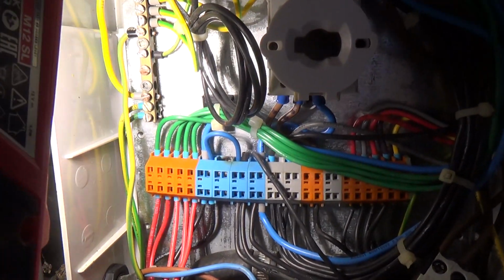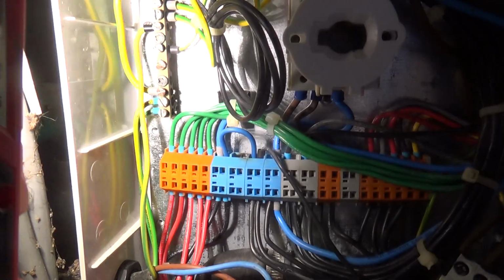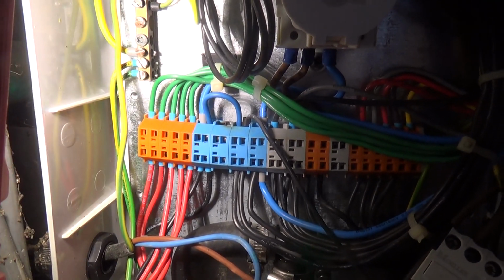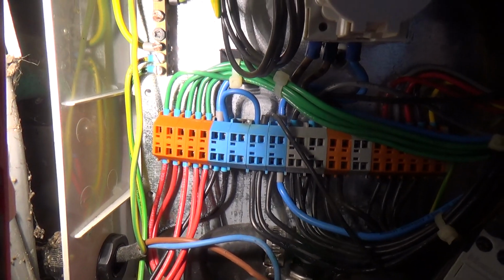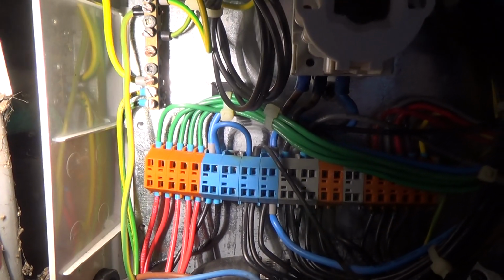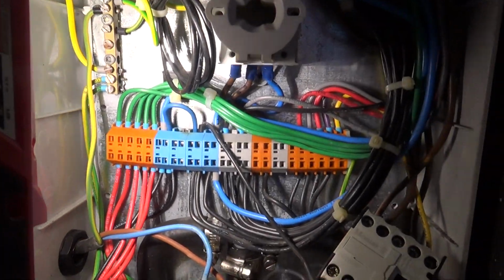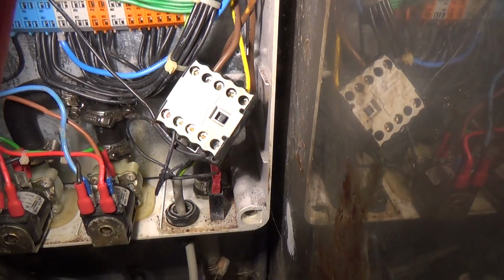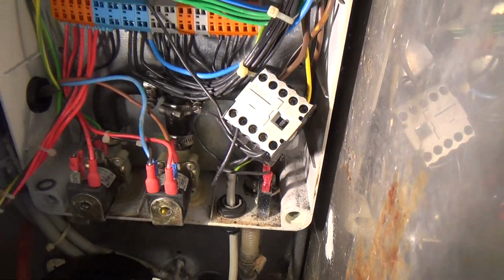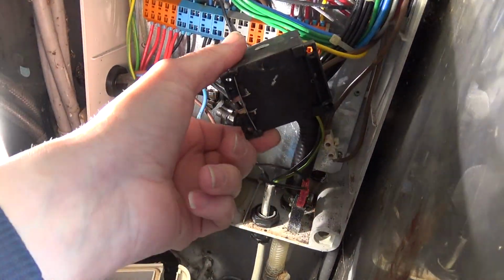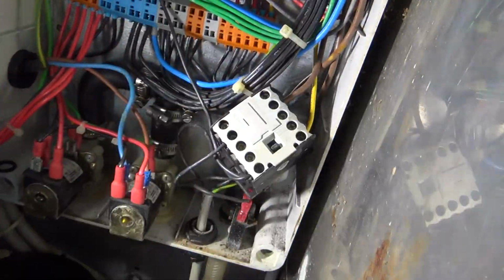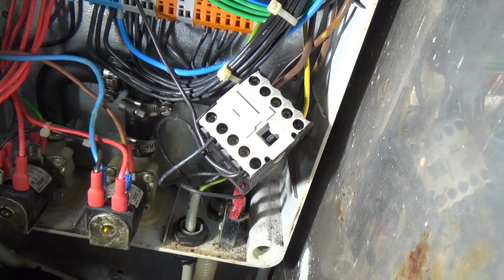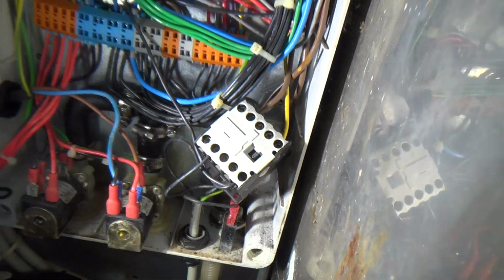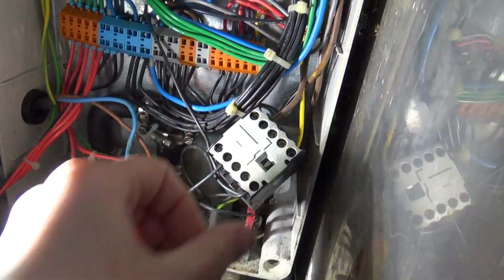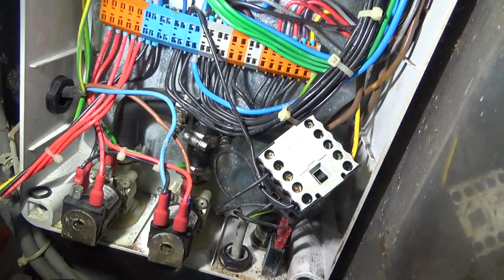I think it's a very small type of DIN rail connector. I'm not sure. If that melted, it could have melted through to the backing plate, but without a jumper across, it's got that jumper in the top, that loop, that centre burnt one is probably not connected to anything, so false alarm there. I think that contact is just floating about. I don't think that's my work, because that's a Moeller contactor which I probably wouldn't buy, so I don't think I'm guilty of that. Not guilty. That's probably just running the agitators.